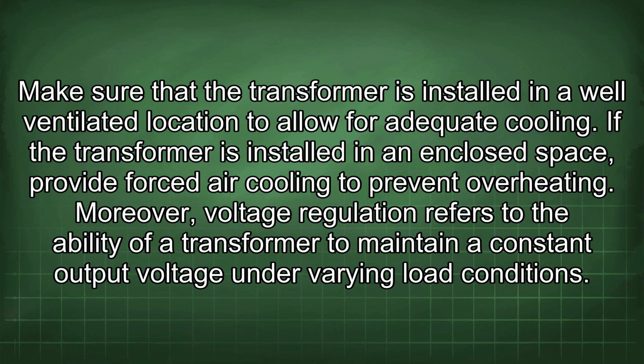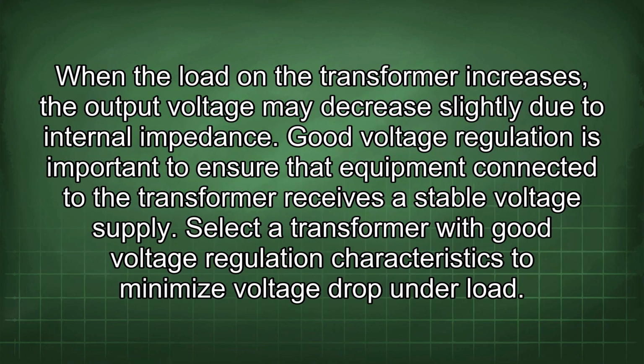Moreover, voltage regulation refers to the ability of a transformer to maintain a constant output voltage under varying load conditions. When the load in the transformer increases, the output voltage may decrease slightly due to internal impedance. Good voltage regulation is important to ensure that equipment connected to the transformer receives a stable voltage supply. Select a transformer with good voltage regulation characteristics to minimize voltage drop under load.